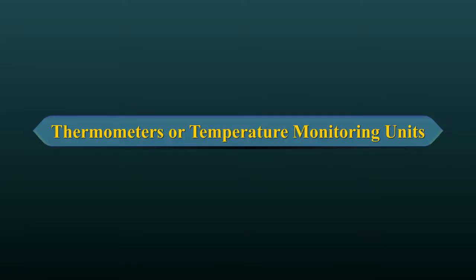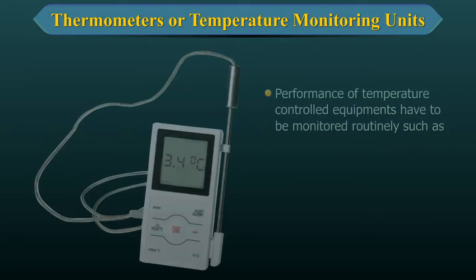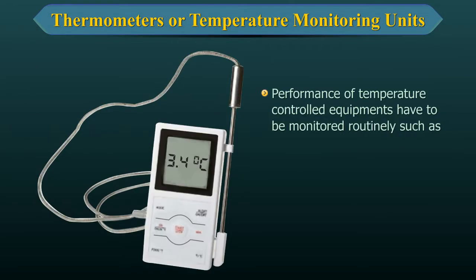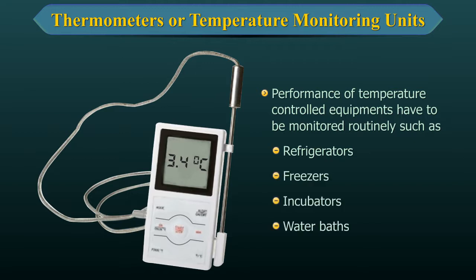Thermometers or Temperature Monitoring Units. The performance of temperature-controlled equipment such as refrigerators, freezers, incubators, water baths, etc., have to be monitored routinely as it influences the integrity of specimens, reagents and test methods, which impact the accuracy of results.